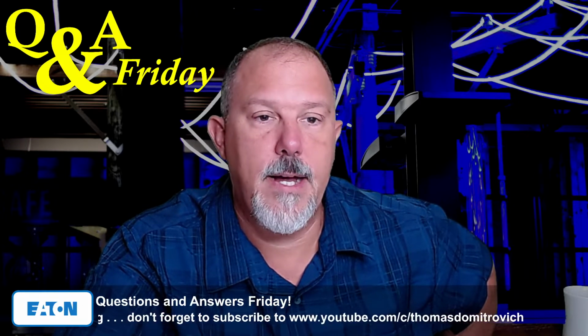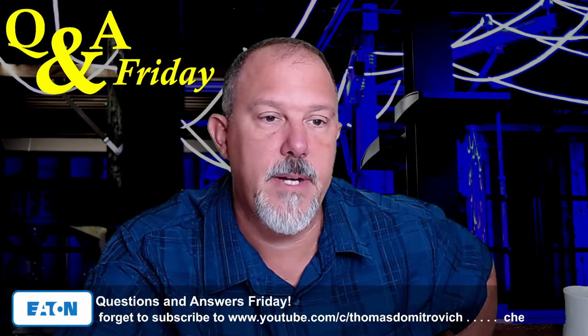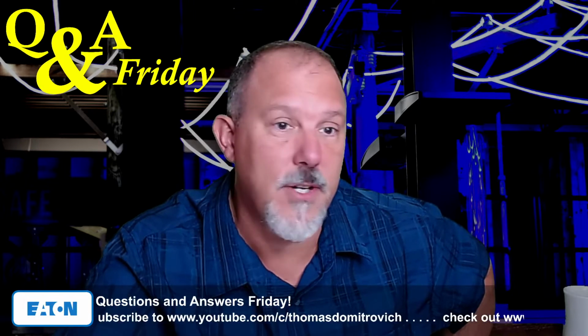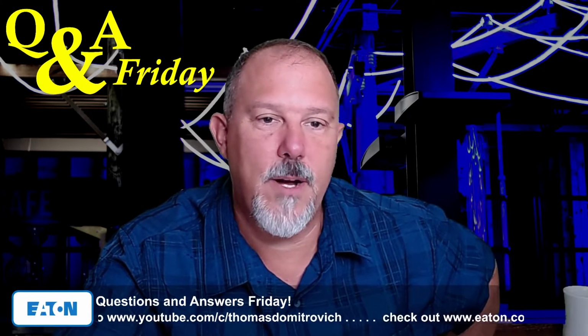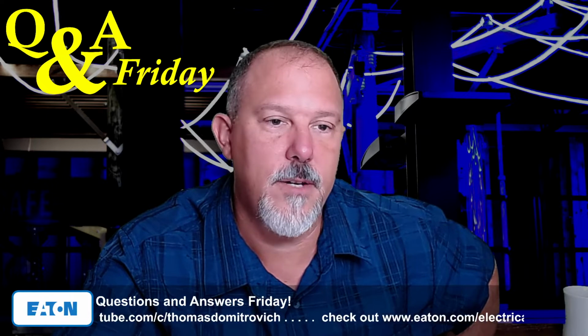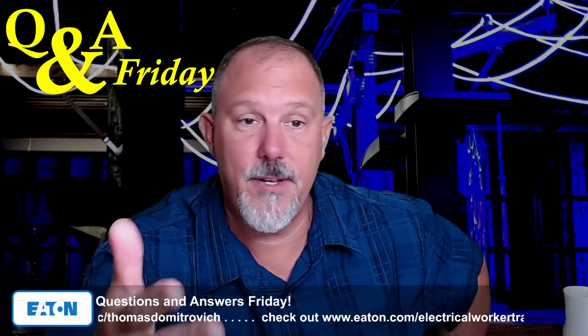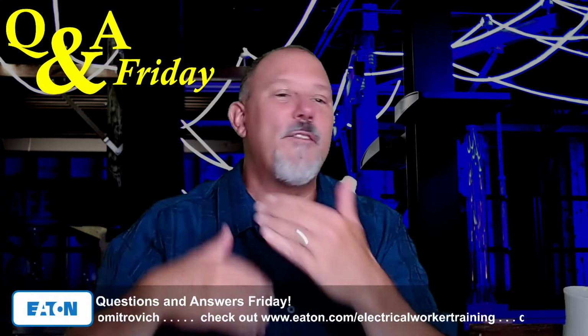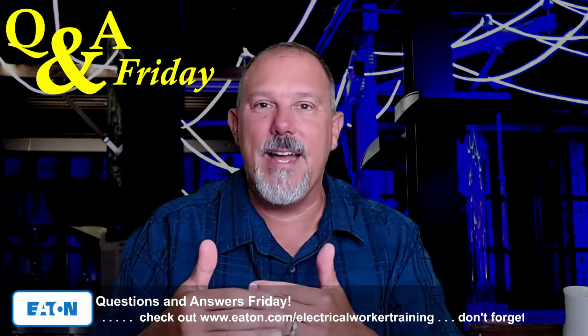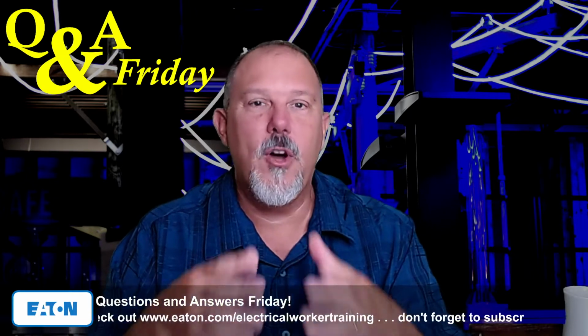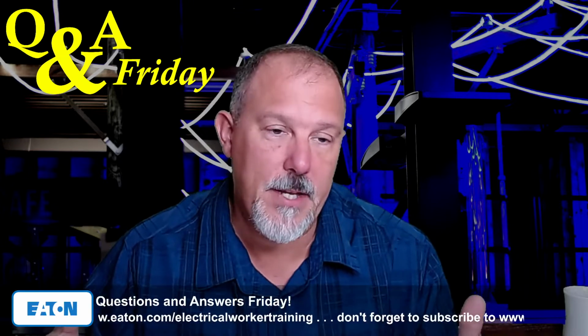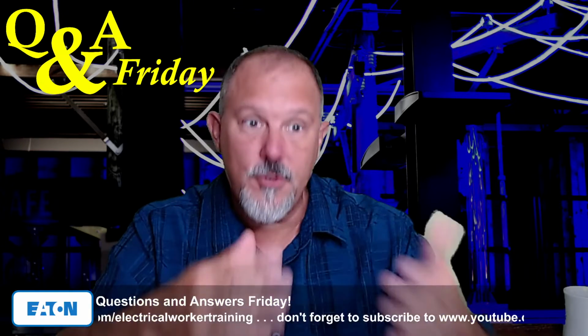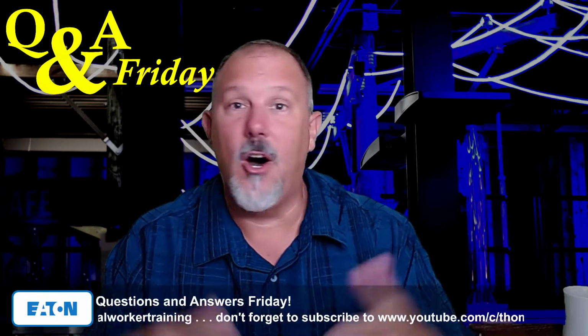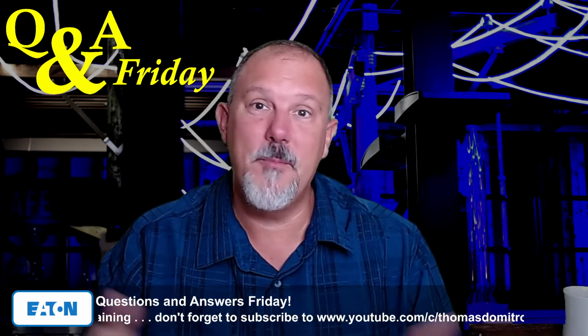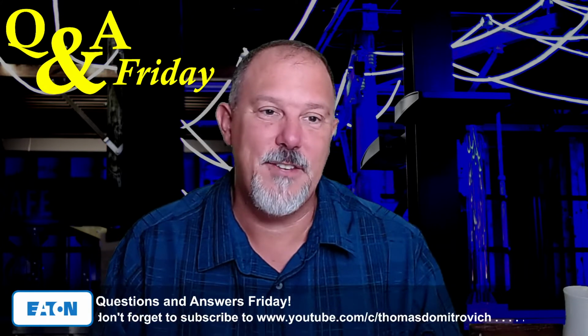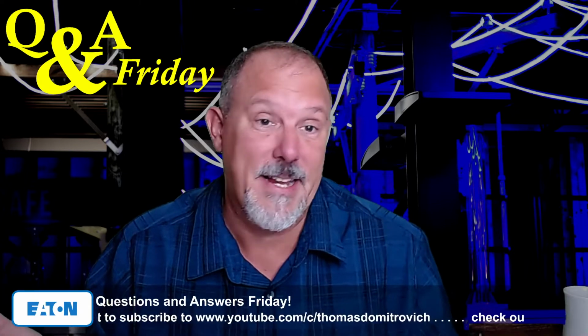Yes, if the ground fault had high enough resistance, a GFCI device might help. Yeah, again, odds are, right? But a properly installed wire type equipment grounding conductor in a dwelling unit would rarely exceed 1 or maybe 2 ohms, right? Again, these conversations, and this is why when we sit at the table, we all have our opinions, and I can respect your opinion. But you're using words like probably, odds are, and I'll use the same words, probably, odds are, and we haven't gained any ground together yet.